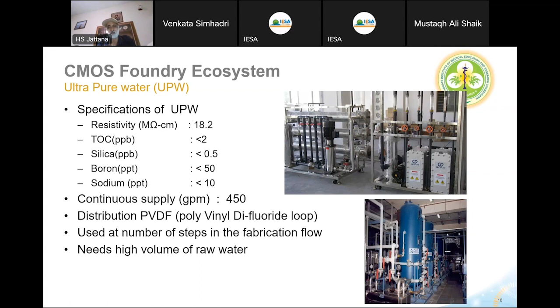It needs a high volume of raw water; maybe for each 500 liters of water, only 1 liter is made ultra pure, and finally it is circulated continuously, whether your batch is running or not. Water cannot be static, because then the whole network will spoil.